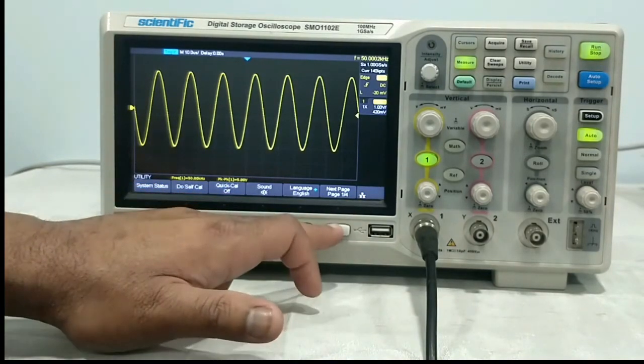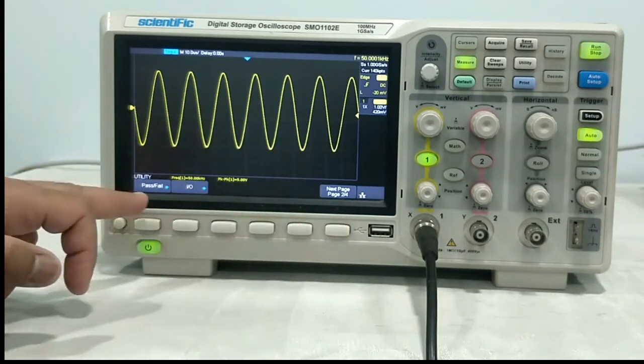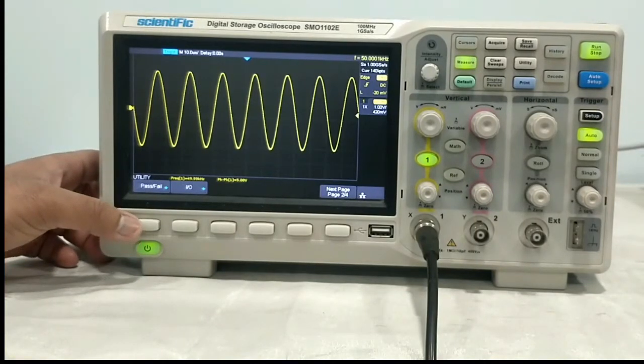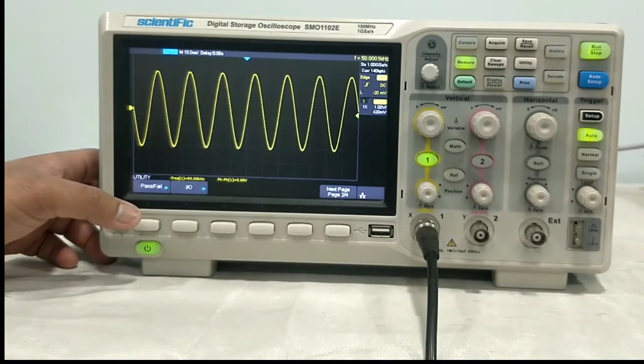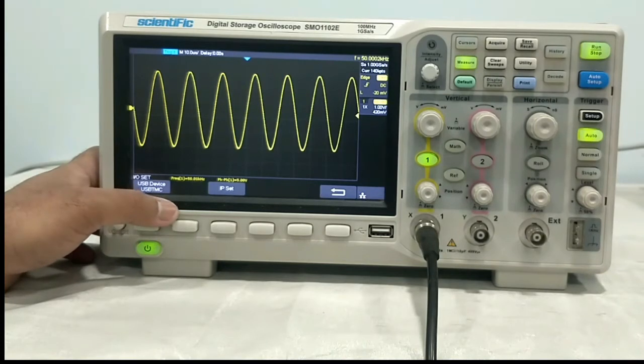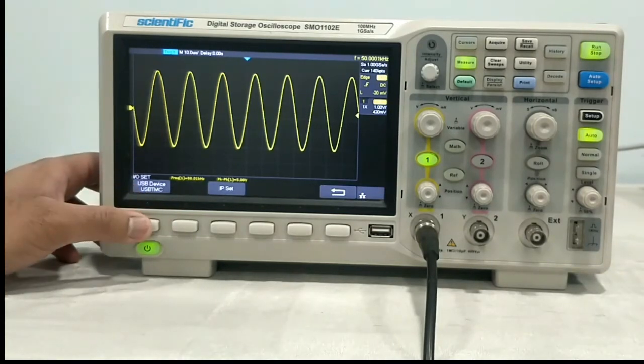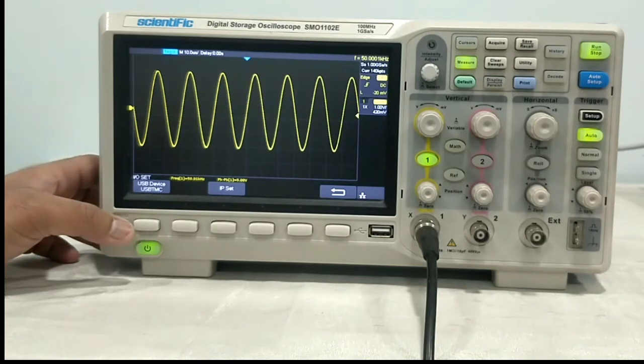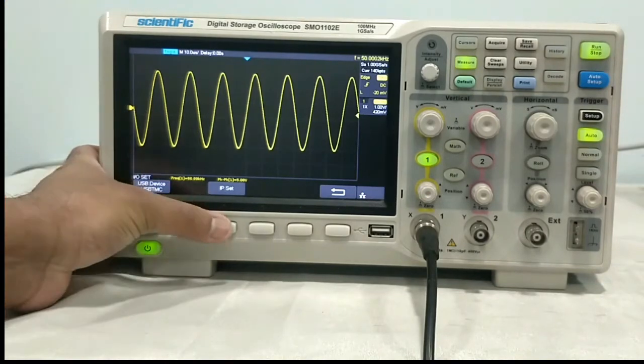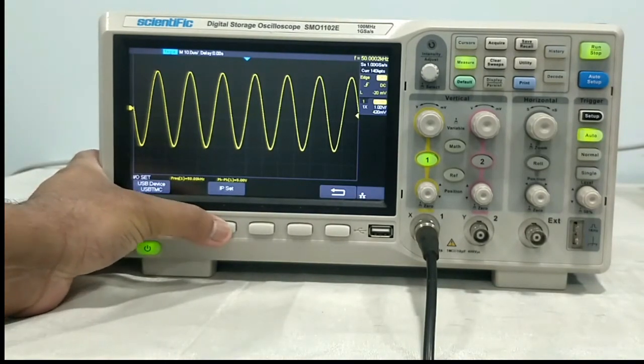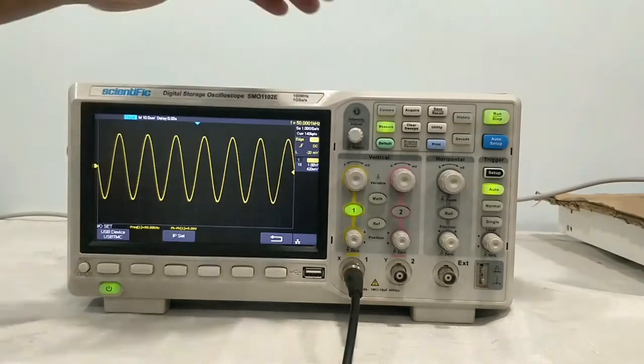Language automatically set to English. In the next page, we have pass-fail judgment. In pass-fail, we have to create a reference waveform — according to the reference waveform, the applied signal will be judged as pass or fail; you have to do masking of the signal. In I/O — input/output — USB device: if you want to control the instrument through PC, you have to connect a USB cable. If you are connecting through LAN, you have to set the IP address. You can go to IP set and set the IP address to interface with the PC. To put the instrument back to default condition, press this default button.